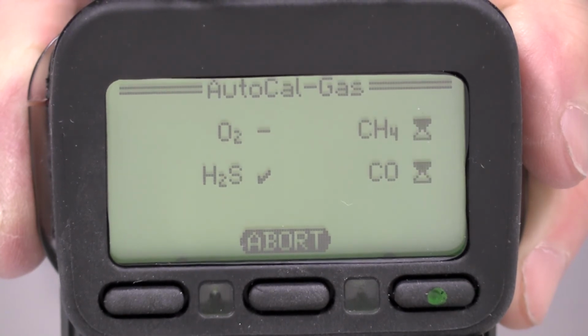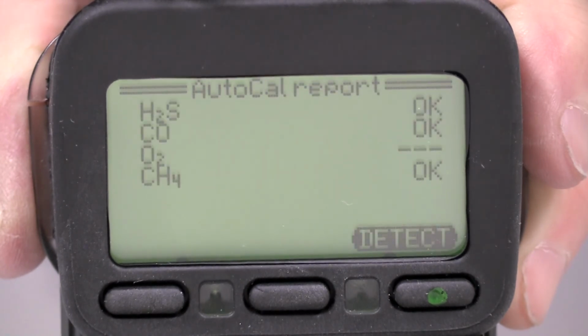An error message indicates the sensor must be serviced, successfully calibrated, or replaced before the instrument can be returned to normal service. The O2 sensor is not adjusted during the gas autocal procedure. The O2 sensor is adjusted during the air autocal procedure.